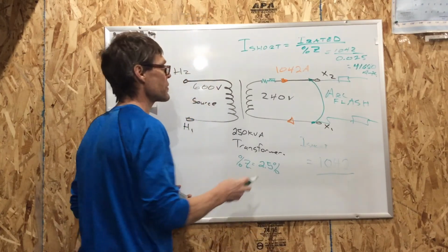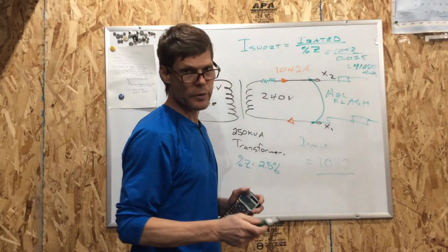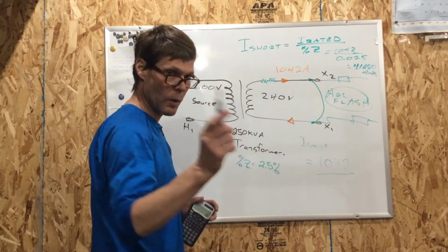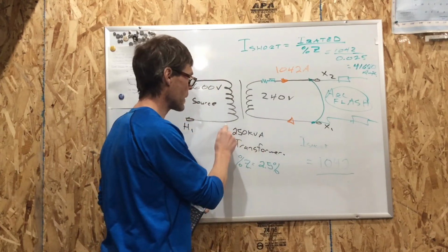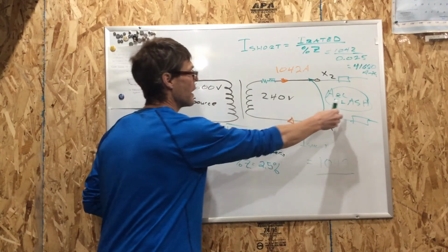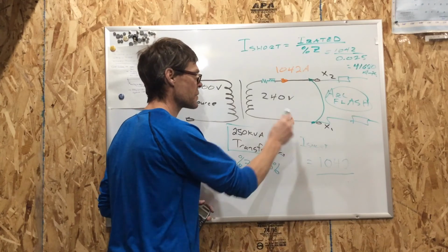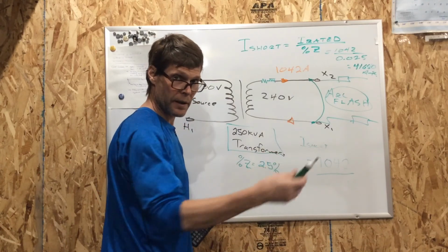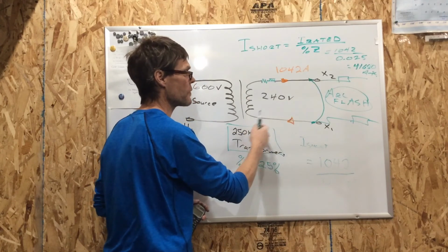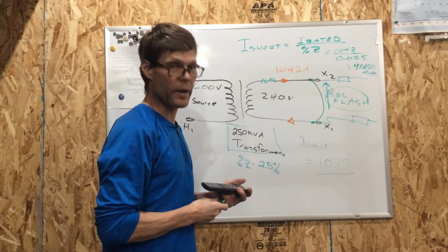So, I short circuit, something to think about here. How much danger are you putting yourself in when it comes to arc flash? Well, I want you to think about how big is the source, how close are you working to the source, and is the source live? And as you get closer to the source, working live, and it's a big transformer, your arc flash hazard is going to go up, way up.